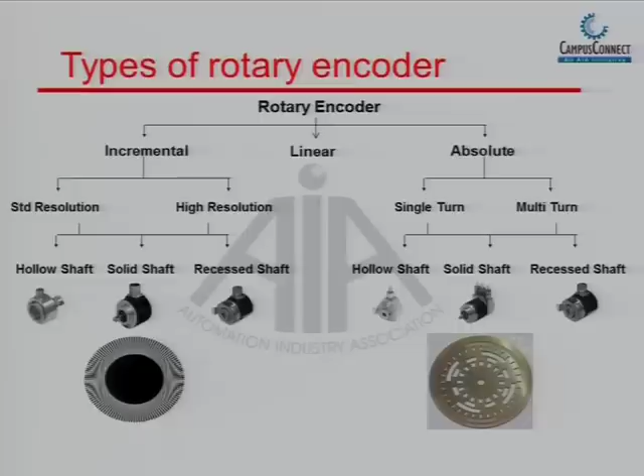If we talk about encoders, there are different types of mechanical structure: hollow shaft, solid shaft, and recessed shaft. Hollow shaft means you can put the motor shaft inside it. Recessed is a similar concept. Solid shaft means you need a coupling between the motor shaft and the encoder shaft. As the motor rotates, the encoder shaft rotates and we get pulses.